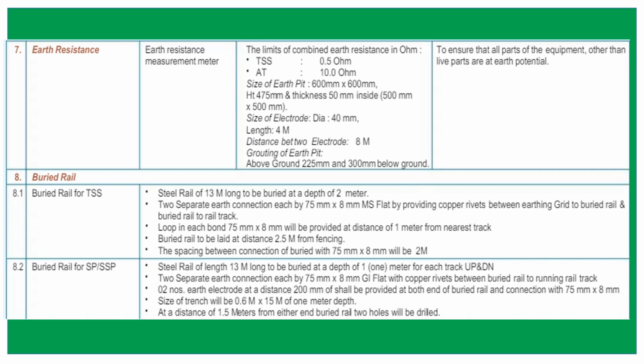Then buried rail. What is buried rail? We are connecting a spare traction rail, that means which is not in use. Its length is 13 meter. One piece is 13 meter without welding. So this buried rail is buried 2.5 meter away from the fencing, below 2 meter, and we are forming holes in the buried rail to connect the traction rail, and the distance between the two holes should not be less than 1.5 meter. 1.5 meter, and the size of the bond is 75 into 8 millimeter MS flat.